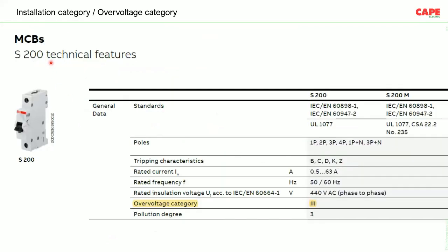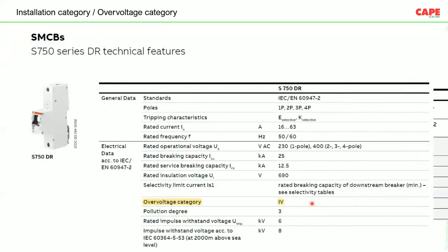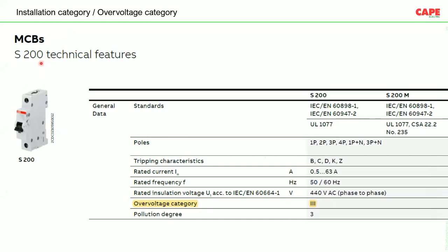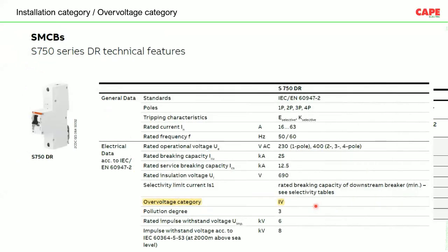That is the meaning. Similarly, another MCB with over voltage category 3 means that at the mains incoming, you cannot use this MCB. You have to use it at the sub switch board or at the fixed part of the installation. Another MCB, S750 ABB, has over voltage category 4. That means at the mains incoming panel board, you need to have this particular MCB, not the previous one. So here, S200, you cannot use it in the mains incoming because it is over voltage category 3. The second one, over voltage category 4, means 6 kV it can withstand minimum. So you can use it at the mains incoming panel.